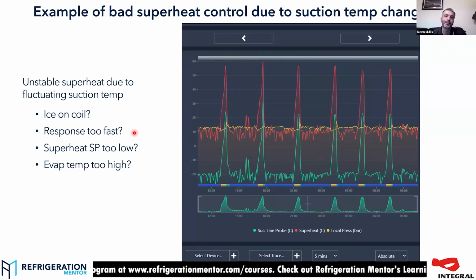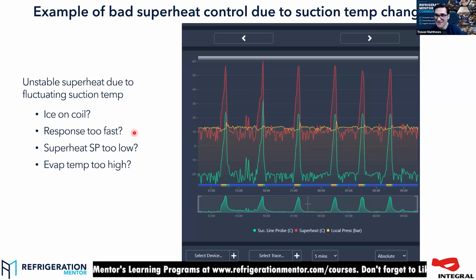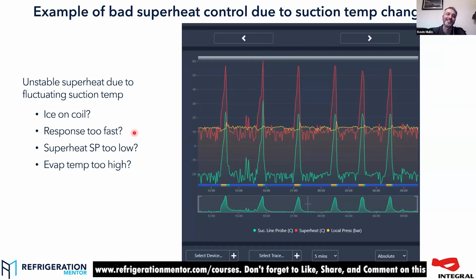And I think it's really important that if you've got an unstable system like that, you understand why. Is it just because of the load changing rapidly? Is it because it just needs to react slower for that type of coil, because of that type of system? You need to understand why it's doing what it's doing. How is it piped? Exactly that, yeah. Has the customer got a tendency to cover the return air grill with things? All things that can affect the performance of the coil. You might need it to react fast for some reason, but don't just go to fast reaction as the first port of call, because you will make the system unstable.